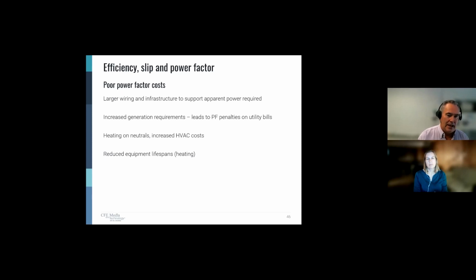Because of this, it trickles all the way back to the power company, and they have increased generation requirements because they're generating a lot more energy that we're wasting in volt-amps reactive because of our poor power factor. In some cases, depending on where you live, utilities will put a penalty on power factor under a certain amount. A lot of times it's 85%. Some places I've seen it as high as 90%. If you don't have better than 90% power factor, you get hit with a penalty on your utility bill. So it can be real money.